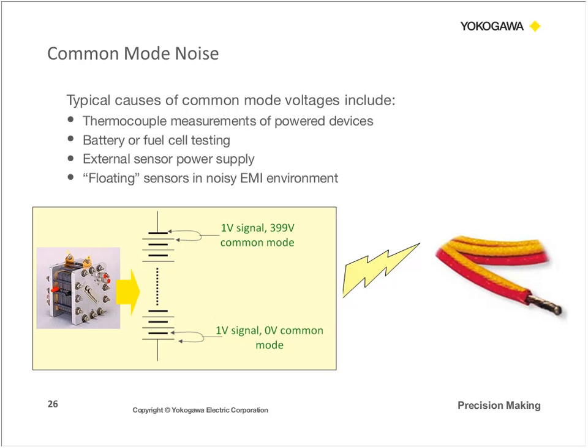And as an example, let's say you have a 1-volt signal at one battery cell, and that is the reference to ground. In reference to ground, there is 0 common mode voltage. Now, let's say you have the second, the third, or even the 4th battery cell where you're trying to measure that 1-volt signal. What's going to happen is, because there's common mode voltage in between that cell in reference to ground, you're going to see that the actual measurement is going to be 1 volt plus that 399 volt common mode signal, and that's going to result in a 400 volt measurement. Well, obviously, you're looking for a 1 volt measurement, and that's not correct.